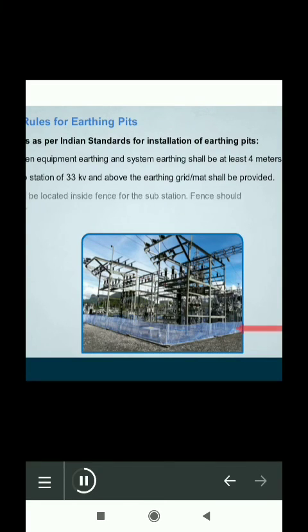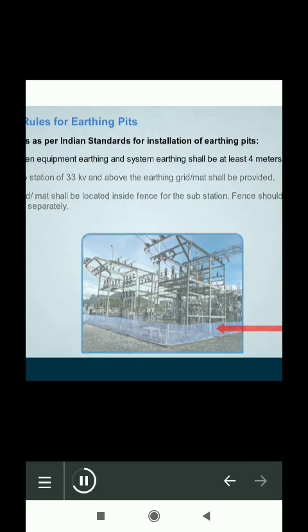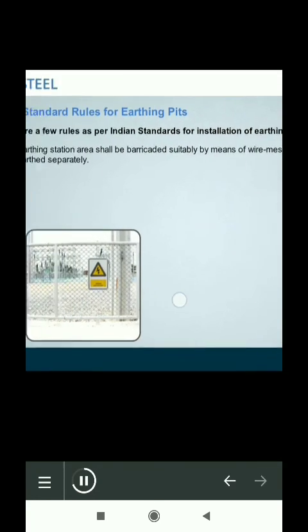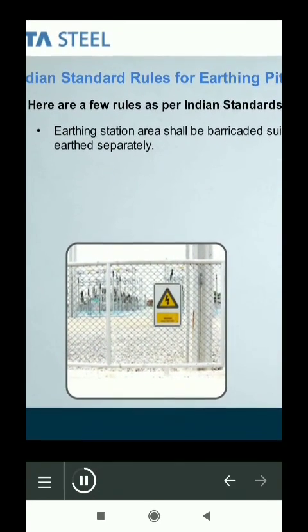For outdoor substation of 33 kV and above, the earthing grid or mat shall be provided. The earthing grid or mat shall be located inside the fence for the substation. Fence should also be earthed separately. Earthing station area shall be barricaded suitably by means of wire mesh fencing and it shall be earthed separately.